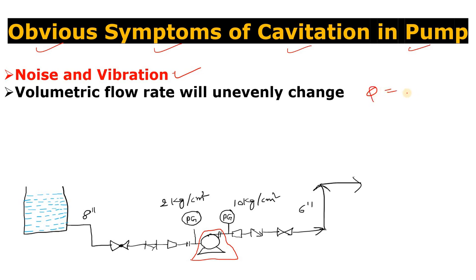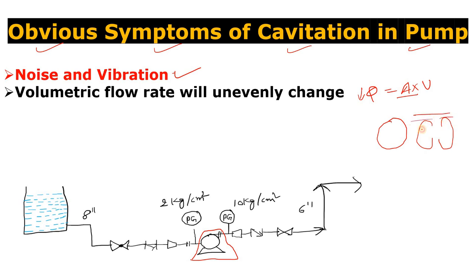Q is equal to area multiplied by velocity. The area for the pump is constant. As there is bubble formation due to cavitation, the bubbles reduce the effective area, so the volumetric flow rate Q will be reduced. When the bubble collapses, the area becomes available again and Q increases. So as bubbles form, Q reduces, and as bubbles collapse, Q increases — that is why the volumetric flow rate unevenly changes. This is a very important symptom to check if you suspect cavitation.